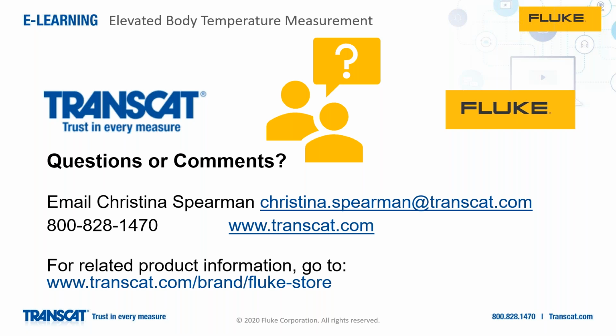In addition, as reviewed earlier, wind, sun, and rain all have an effect. For the FS100, per FDA guidance and IEC specifications, the ambient temperature range for the environment needs to be between 18 and 24 degrees C, with operating humidity of 75% or less, non-condensing. So there are going to be a lot of places where taking a measurement outside just won't work, especially under direct sunlight or with airflow.